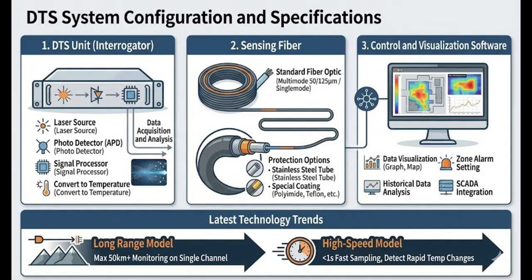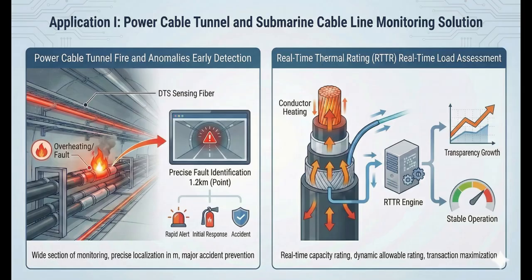A DTS system consists of 3 parts. First, the DTS interrogator, which includes the laser, detector, and signal processing. Second, the sensing fiber and its protective structure installed in the field. And third, visualization software that displays temperature profiles like a map and supports alarms, trend history analysis, and SCADA integration. Recently, both long-range single-channel models, capable of monitoring tens of kilometers, and high-speed models with sub-second sampling are being widely adopted. In utility tunnels and underground transmission lines, DTS provides 2 key values.